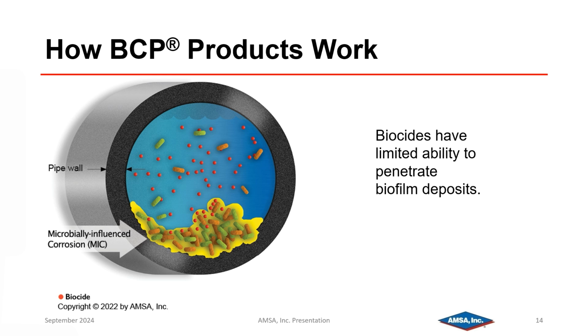While it's not accurate that biofilm deposits all settle in one spot at the bottom of a pipe in a cooling water system, it is accurate that most of the bacteria in the system is located within the biofilm deposit. It is estimated that 90% of bacteria in a cooling water system is indeed in biofilm deposits. So the rod-shaped bacteria that are floating in the bulk water, or planktonic bacteria, represent just about 10% of the bacteria in a cooling water system.